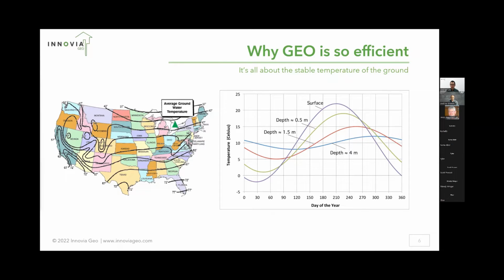What I'm showing in this figure on the right is the ground temperature across a year at different depths from the surface. This purple line fluctuates quite a bit because we're close to the surface. In the wintertime we're getting below zero, and in the summertime we're getting to above 20 degrees Celsius. But as we get deeper into the ground, that fluctuation through the year gets less and less. By about 30 feet deep, that fluctuation is pretty minimal, and we're at a stable ground temperature all year round.